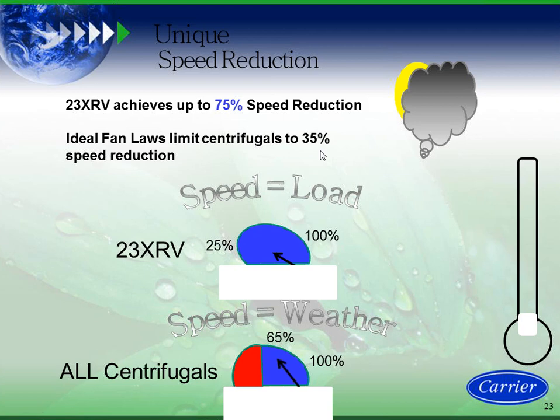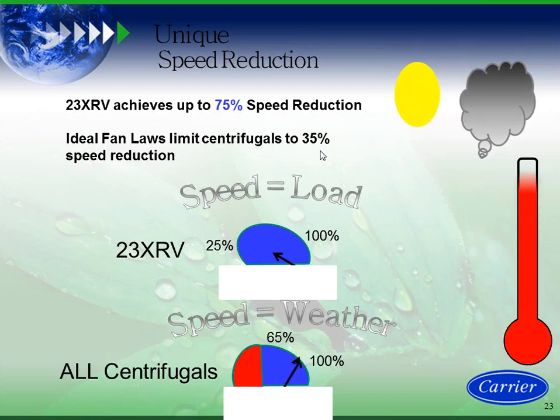Now my load doesn't change dramatically when the sun comes out. It will change eventually, but it doesn't change dramatically. But what happens on a centrifugal machine? The sun comes out, it's now not overcast, and my tower water, my wet bulb temperature, shoots up. Because the centrifugal is a part lift device, it then has to track the weather. So the speed of my VFD ramps up. The 23XRV is still able to just maintain the load in the space. It is not a part lift device; it is a part load and part lift device. So that's why the 23XRV is so much more efficient than a centrifugal.